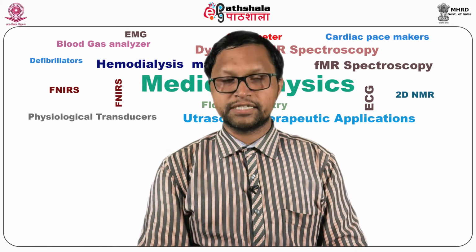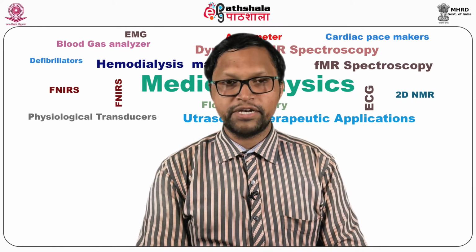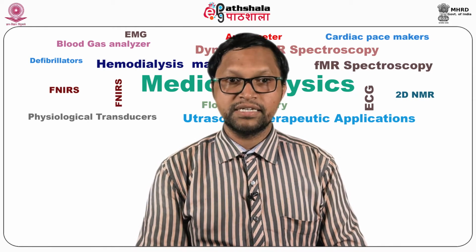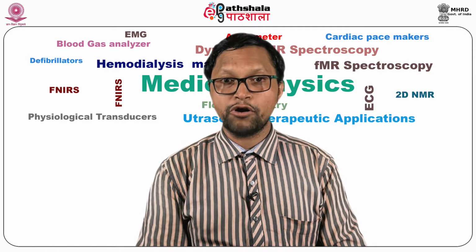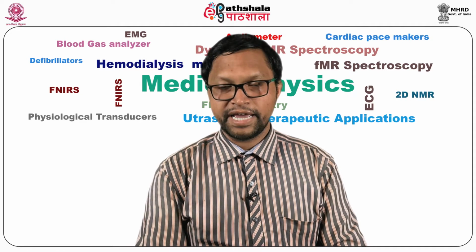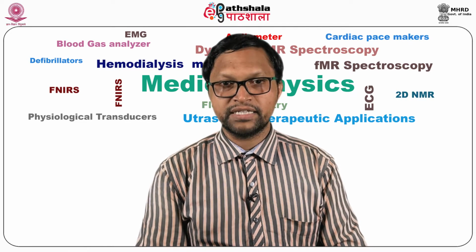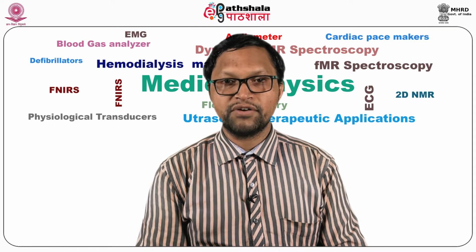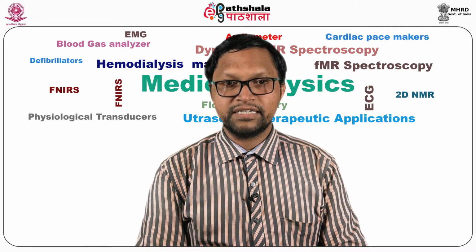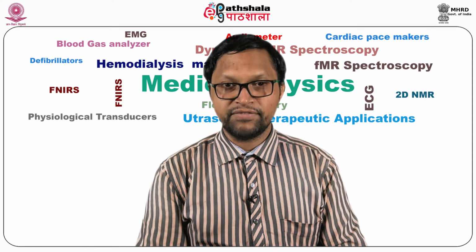Functioning of the pacemaker system. The essential requirement from a pacemaking machine is that it delivers precisely timed small output electrical pulses. Hence, there are two vital things which this device requires. First, a timer, and second, the power source for delivering the impulses.